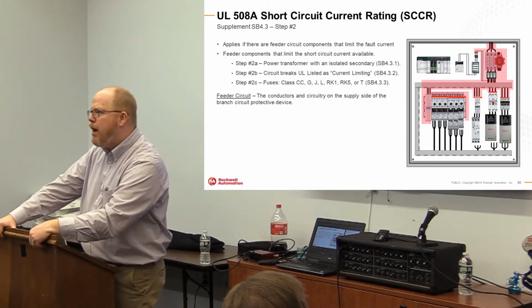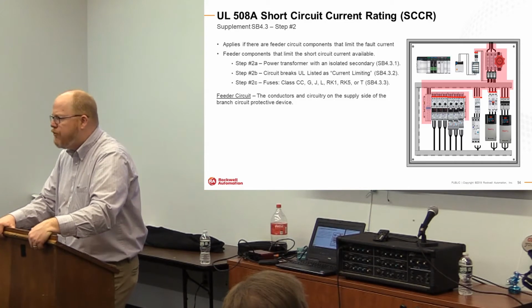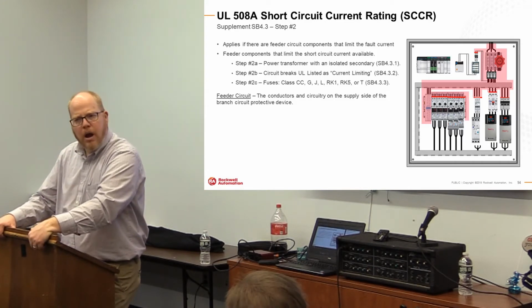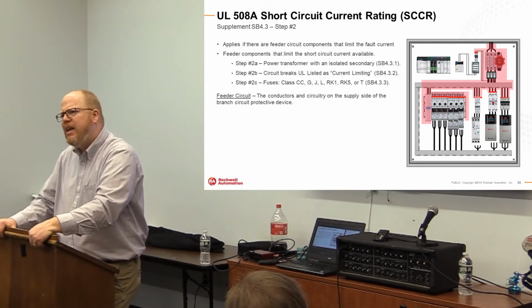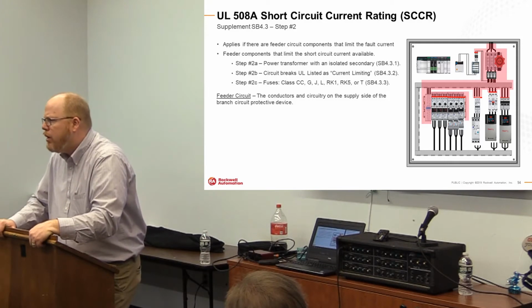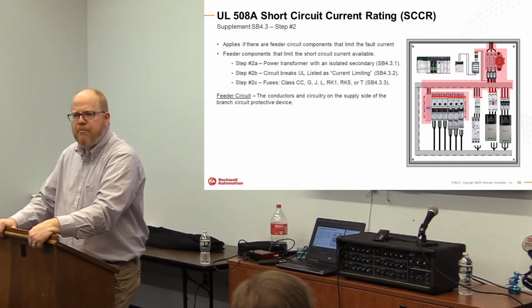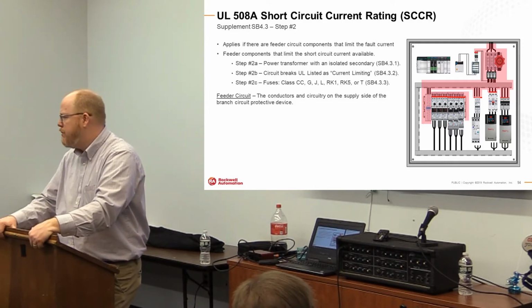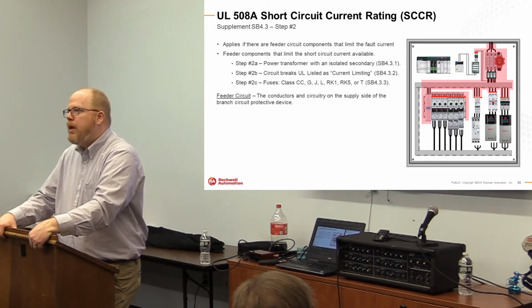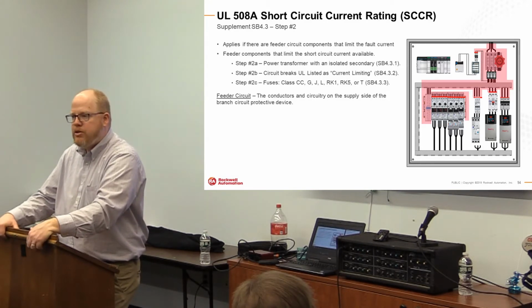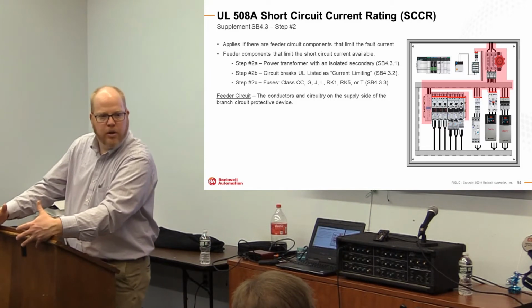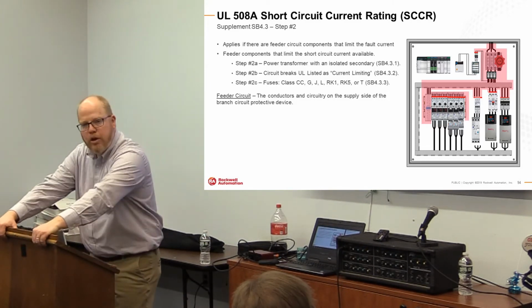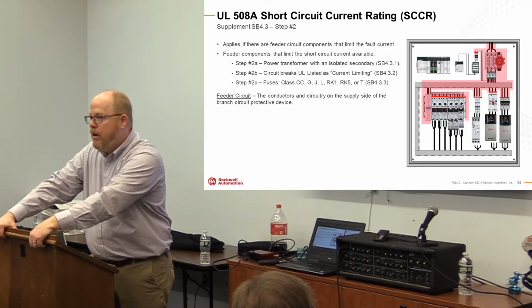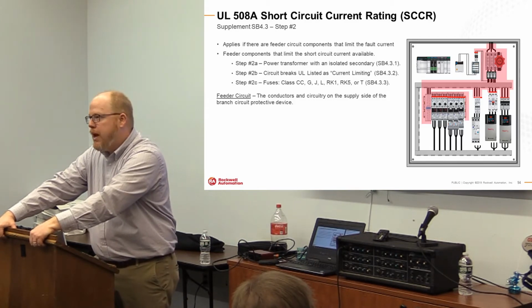I can tell you right now, fuses through their physical characteristics are inherently current limiting, and they kind of get the benefit of the doubt according to the UL document. They've been viewed as current limiting devices for many, many years. As with circuit breakers, current limiting circuit breakers are engineered devices for current limiting, right? So you have to look and review trip curves and let-through values from the actual manufacturer.